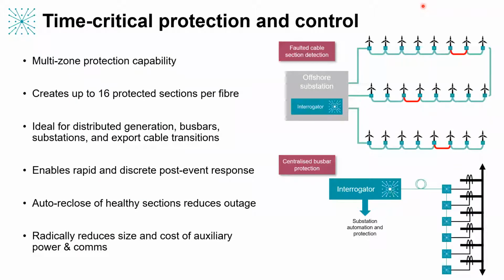I won't get into too much detail today on the different applications, but for example, in protection there are some great applications. In offshore, here in the top right, you can see that with this system we're able to instrument entire arrays of offshore turbines at a granular per-turbine level. With one system, we're able to do fault detection on individual intra-array cables. We can trip breakers along there if they are in the system or built in for this. At each cable terminator we've got the temperature live, we've got the power quality on every turbine live, and we've got the synchrophasors at every turbine. All of that from a single system rather than having three or four different systems which require a supervisor to intervene and correlate. And likewise, you've got similar centralized protection and asset management schemes in substations, on or offshore.